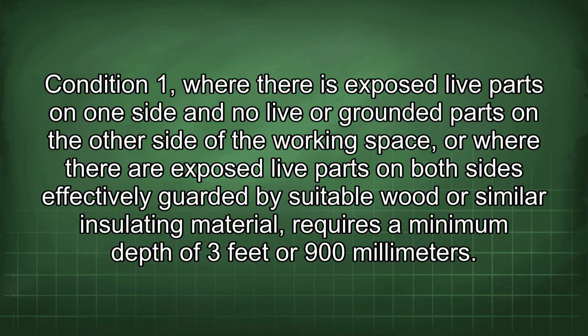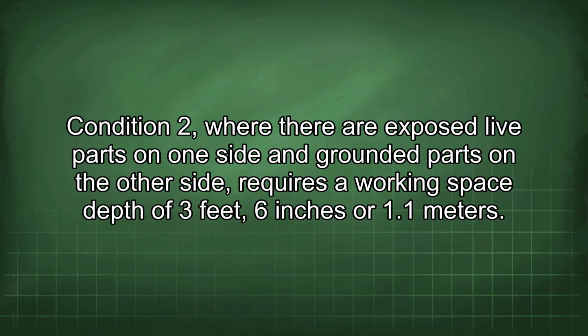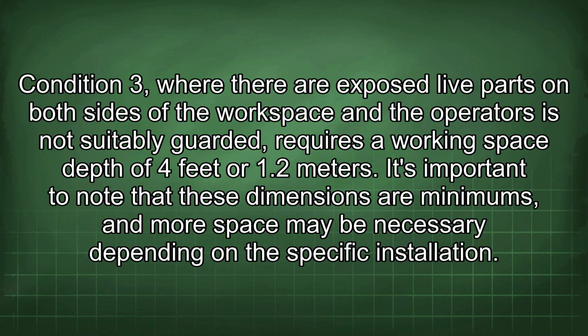Condition 1. Where there are exposed live parts on one side and no live or grounded parts on the other side of the working space, or where there are exposed live parts on both sides effectively guarded by suitable wood or similar insulating material, requires a minimum depth of 3 feet or 900 millimeters. Condition 2. Where there are exposed live parts on one side and grounded parts on the other side, requires a working space depth of 3 feet 6 inches or 1.1 meters. Condition 3. Where there are exposed live parts on both sides of the workspace and the operator is not suitably guarded, requires a working space depth of 4 feet or 1.2 meters.